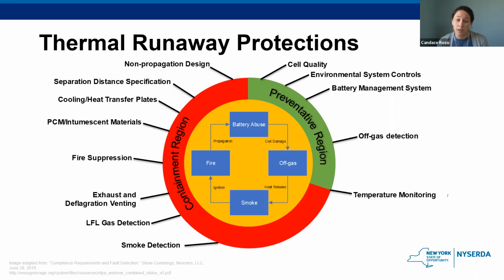Once the system starts to smoke, you are now in containment mode, as the system is in a thermal runaway event. As you can see, as the event progresses, there are more safety measures in place to contain it. So you'll hear more about each one of these controls as we go through the code. And just as awareness, everything we are going to speak about going forward is in the New York State Uniform Code, so you won't need a local adoption, as these protections are already required. So really just giving you a quick snapshot of what the risk with energy storage is, and mostly it's concerning thermal runaway, and how these systems are being designed to make sure that this sort of event doesn't happen. And you can see all the protections, preventative and containment, on the screen, and mostly embedded into the code itself.